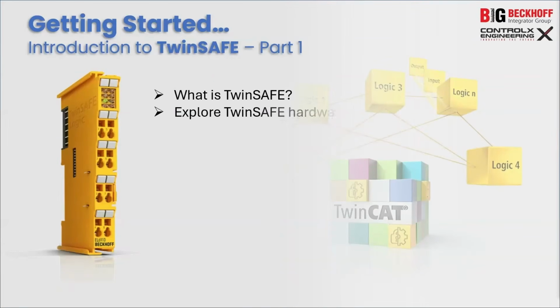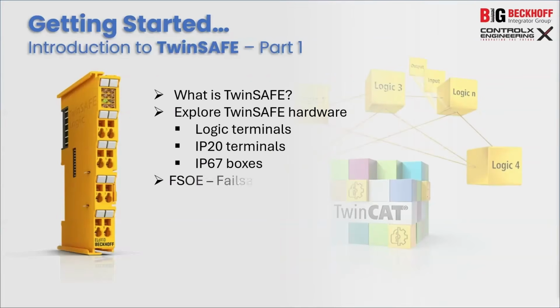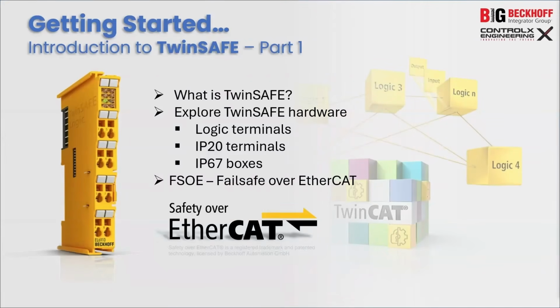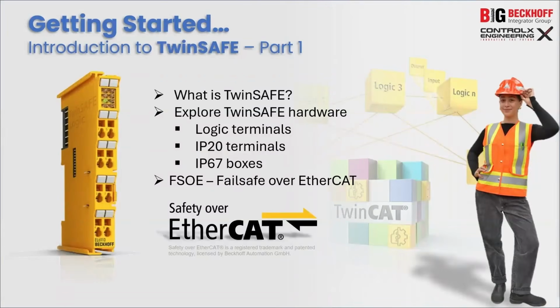In today's episode, we will review what TwinSAFE is and look at the safety product offering from Beckhoff Automation, which covers the logic terminals as well as multi-channel safety input and output terminals, which come in both IP20 DIN-mounted terminals as well as field-mounted IP67 boxes for remote safety inputs and outputs. We will also explore the safe communication protocol, FSoE, which is an abbreviation for fail-safe over EtherCAT. So put on your safety gear and let's get started.